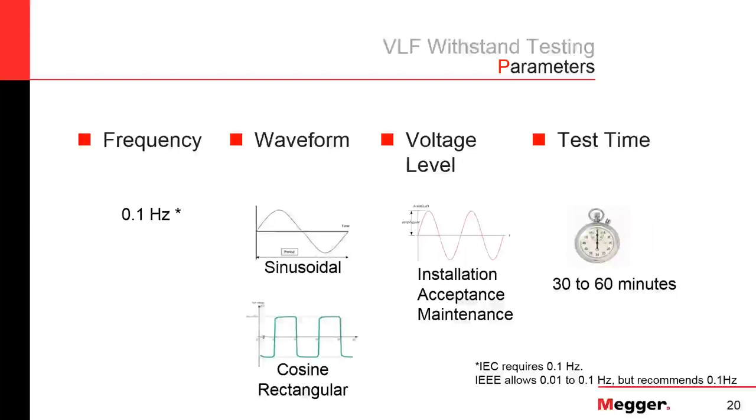So the parameters for VLF testing: frequency is 0.1 hertz. We can use sinusoidal or cosine rectangular waveforms. Voltage level would be acceptance testing, installation testing, or maintenance testing based on where we are in the lifetime of the cable. And the test time is 30 to 60 minutes by IEEE. For more information on installation testing and acceptance testing, we have a webinar from, I guess, last year where we go into more depth on this.